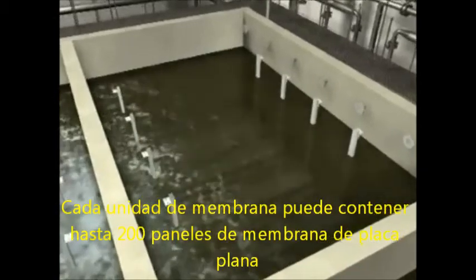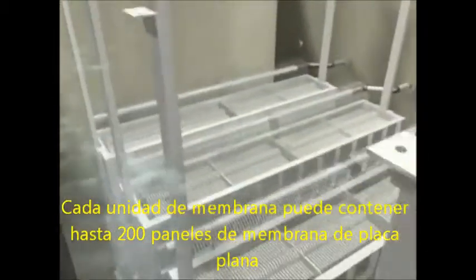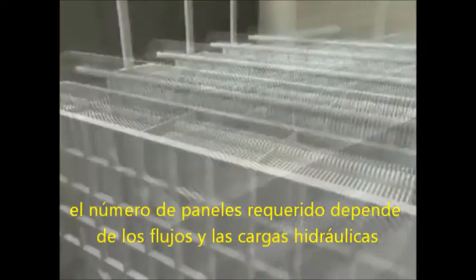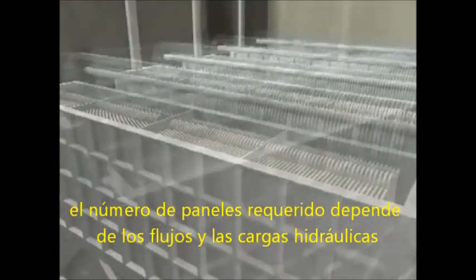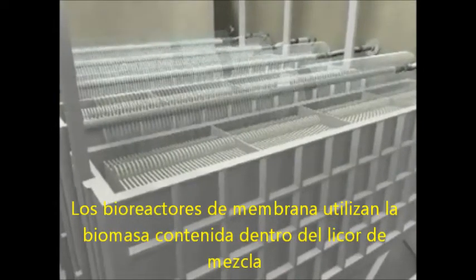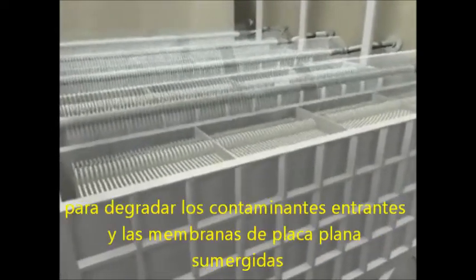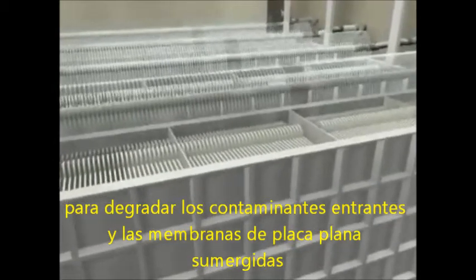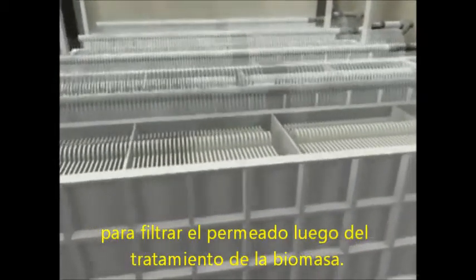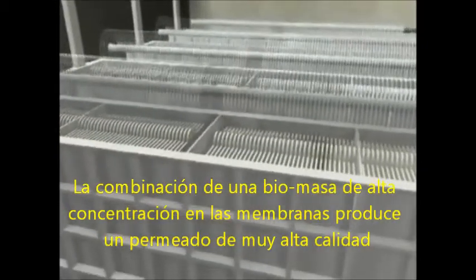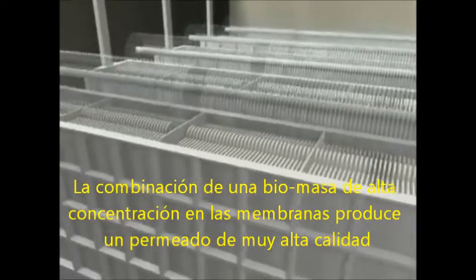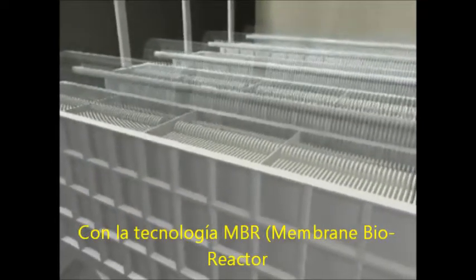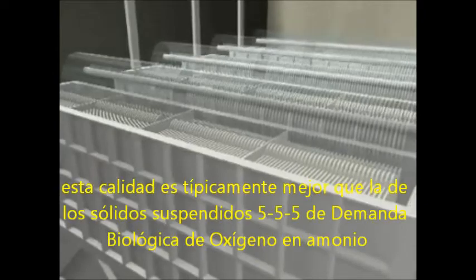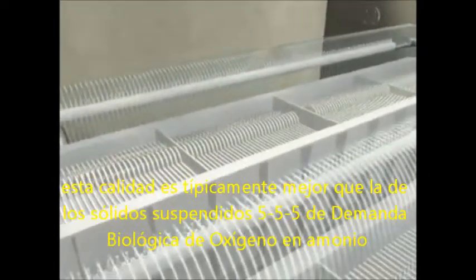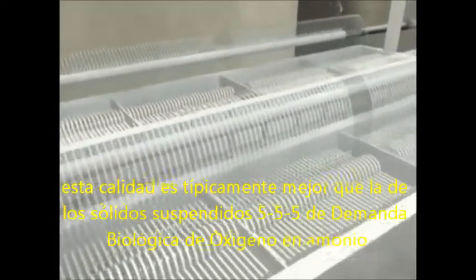Each membrane unit may contain up to 200 flat sheet membrane panels, the number of panels required being dependent on hydraulic flows and loads. Membrane bioreactors utilize the biomass contained within the mixed liquor to degrade the incoming pollutants, and the submerged flat sheet membranes to filter the treated permeate from that biomass. The combination of the high concentration biomass and the membranes produce a very high quality permeate. With the Aquatil Group's MBR technology, this quality is typically better than 5-5-5 biological oxygen demand, suspended solids and ammonia.